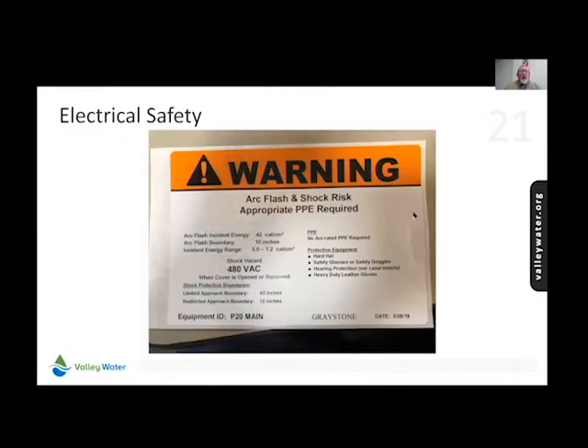We'll go to the next slide here. These are the more appropriate stickers that we're now starting to install throughout our facilities. As you can see here, it tells us this one is 0.42 calories, and says no arc-rated PPE is required, but there's still a shock hazard, so shock equipment is required. If you're making a voltage measurement, you're going to be required to wear a hard hat, safety glasses, hearing protection, and heavy duty leather gloves.